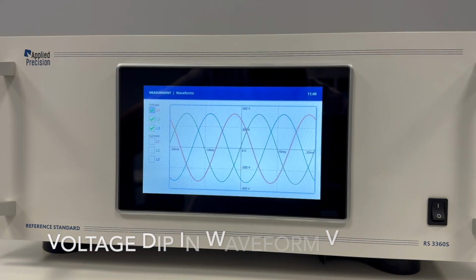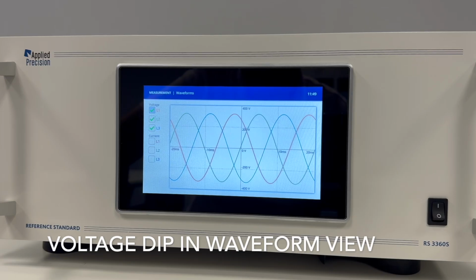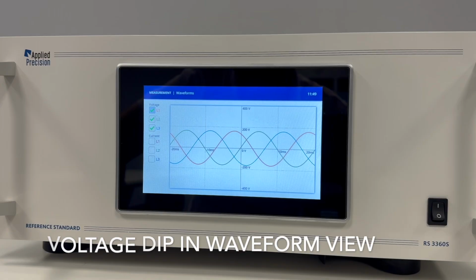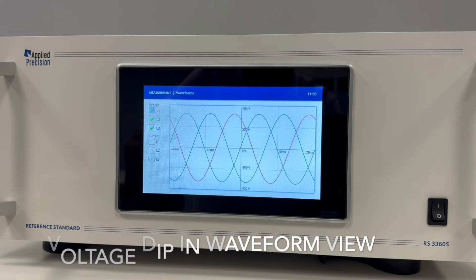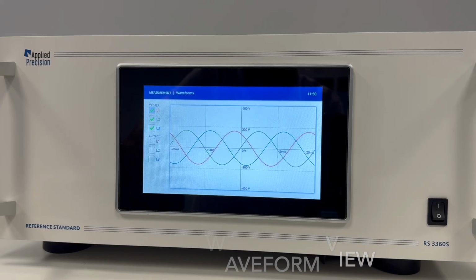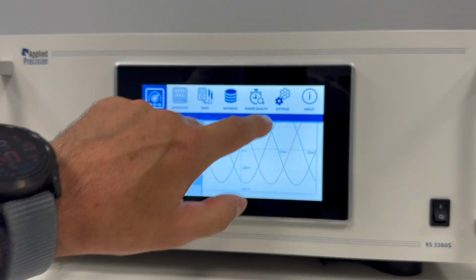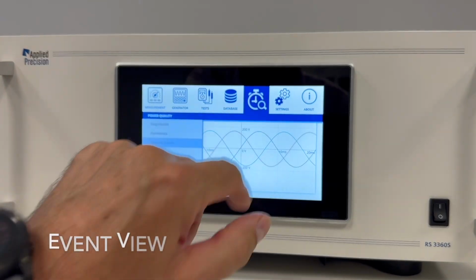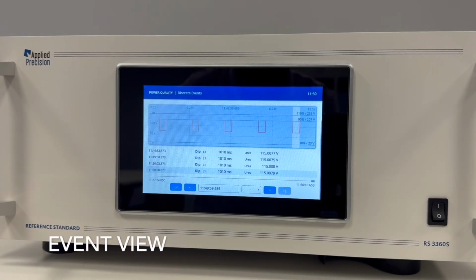And now we can see that for 1 second it will drop down to half of the amplitude on all three phases. This is because of the 50% dip, and for the remaining 4 seconds of the defined repeat period, it is at 100%.